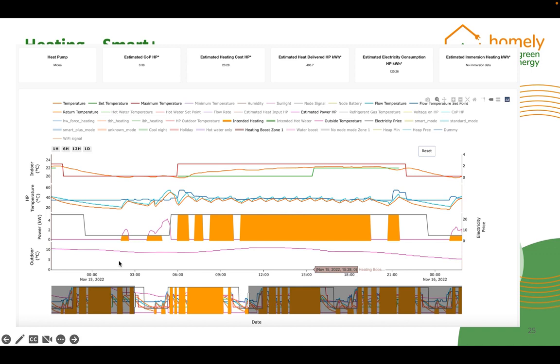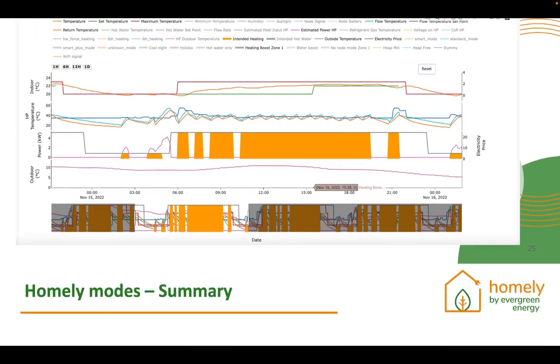This is not the advised way to use the Smart Plus function. If it is for comfort that you're trying to reduce the impact of temperatures in rooms such as bedrooms, it should be just that. In the bedrooms you can turn the radiators off so that the bedrooms stay cool, but the rest of the house should actually be preheating for that day so that you can utilize as much of that cheap electricity as possible. That's what we normally advise customers to do.